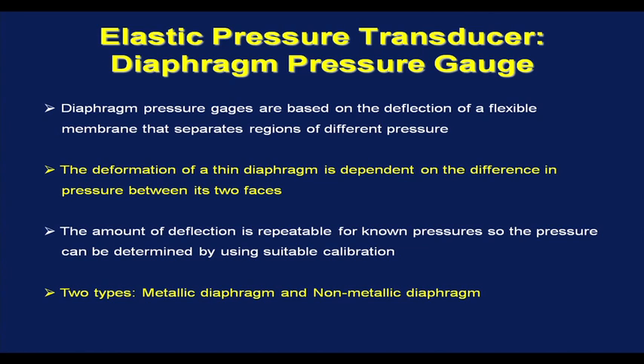So, if I have a thin flexible membrane, let us call it a diaphragm, and two different pressures are being applied on two faces, then the deformation or the deflection of the thin diaphragm will be a measure of these two pressures that are being applied on its two faces. The amount of deflection is repeatable for known pressure, so pressure can be determined by using suitable calibration. Both metallic diaphragms and non-metallic diaphragms are used for pressure measurement.